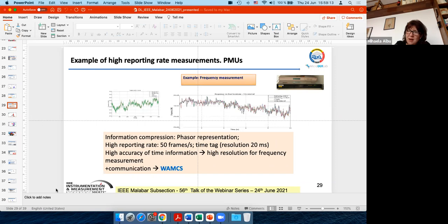But the problem is that inside the measurement equipment there is a tiny decision or processing block that decides, 'I will not give you the information every millisecond because you'll be tired; I'll make an average and give it to you every 10 minutes, just be happy.' What I want to say is we have to question ourselves how the reported value that arrives to us, or to a control system, was obtained — was it measured every 10 minutes, or measured continuously and then averaged and reported every 10 minutes? The difference is huge, because averaging is filtering, and filtering, we know, is loss of information.